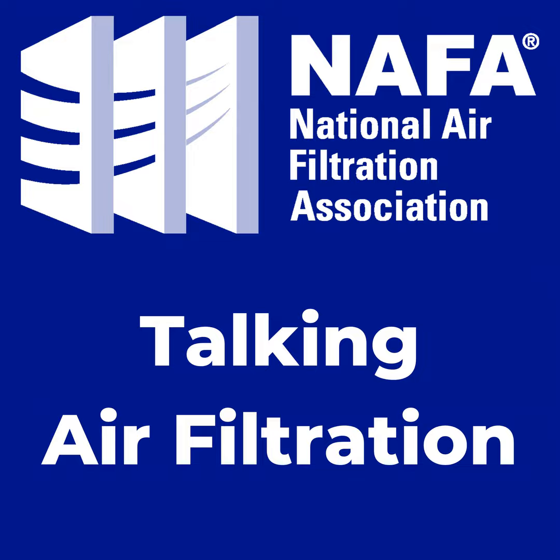So when you have a large fiber and an airstream coming at it, if you're really into the physics of air filtration and airflow, you know that the velocity is roughly zero at the surface of any larger fiber. But the nanofibers are so small that you don't get a zero velocity gradient at that point on the fiber. So this allows better airflow properties through the fibers.